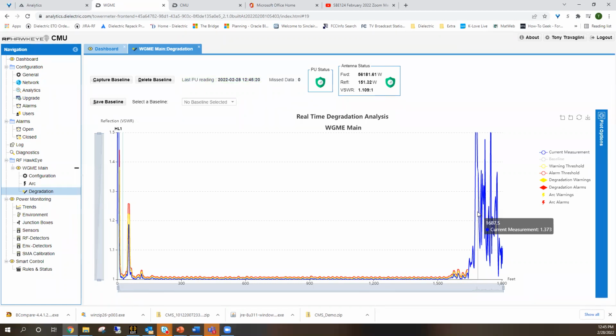And then you can see up top, that gives you your antenna status, which is information from your directional coupler, forward and reverse power. That, in conjunction with the TDR, is how you can tell - if you see an increase in VSWR but don't find any anomalies in the transmission line, you can point your sights towards the antenna. Vice versa, if you see an increase in VSWR and you're also getting degradation alarms or warnings, then it gives you a location. Makes it a lot easier to troubleshoot and takes away the variability of looking for it.